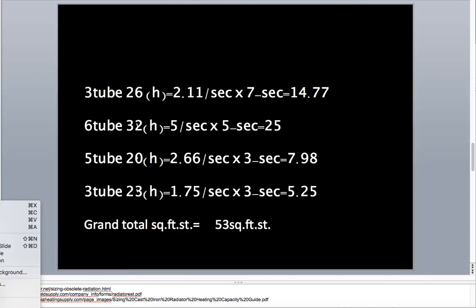So you add those all up. So you get your three-tube, your six-tube, your five-tube, you have a three-tube. You get all your heights here. 26, 32, 20, 23. Your amount of square feet of steam per section. The number of sections. And then your total is your total square feet of steam per radiator. All four of these. This is a small house. 53 square feet of steam. It's just for an example.